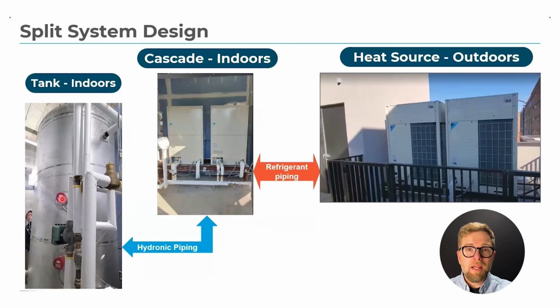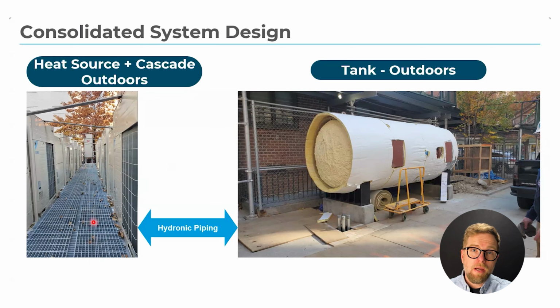The heat source unit and the cascade unit can be installed up to 65 feet apart, horizontally or vertically. That means if your building doesn't have space for both pieces side by side, you can tuck the cascade unit indoors where it's warmer and less exposed while the heat source unit stays outside, or you can put them both outside, whatever suits your layout best.